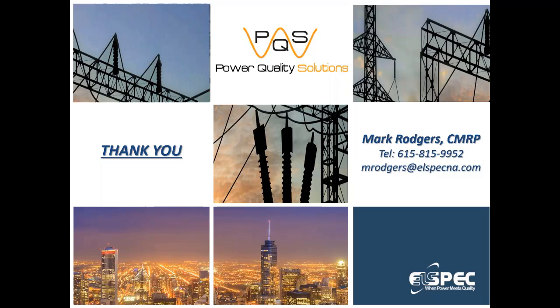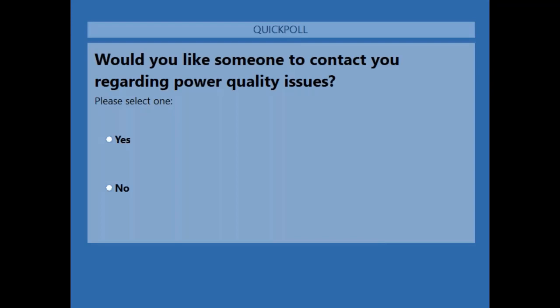And for voltage, we don't really have a top end now, and the reason for that is because our systems are internally low voltage, so we can design the systems for direct connect anywhere up to 690 volts. So for a medium voltage application or even a high voltage application, we just design it at that 600 or 690 volts range and then utilize a step-up transformer to step it up to whatever voltage is necessary. So that could be 13.8, that could be 4160, that could be 120 kilovolts. It's really the sky's the limit, because kVAR is kVAR at any point. So we just step it up to whatever the voltage network needs to be.